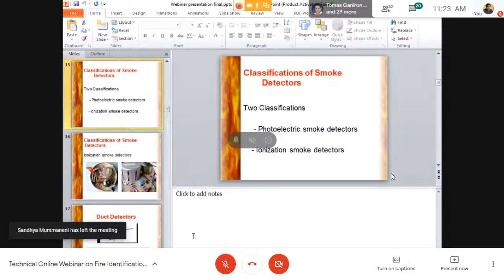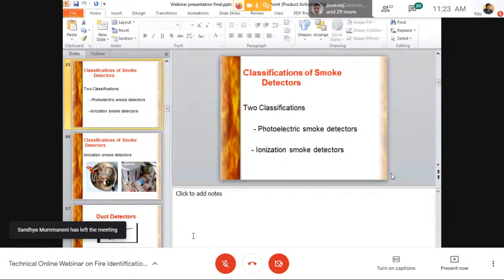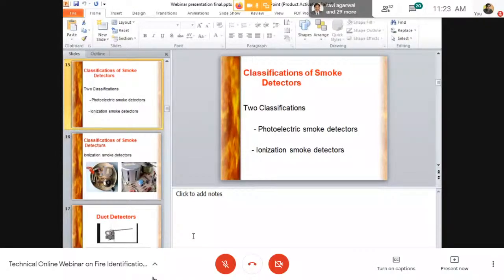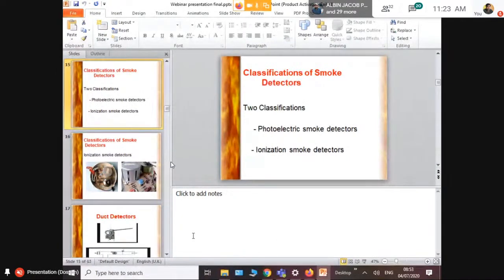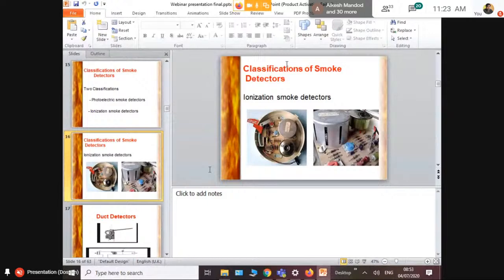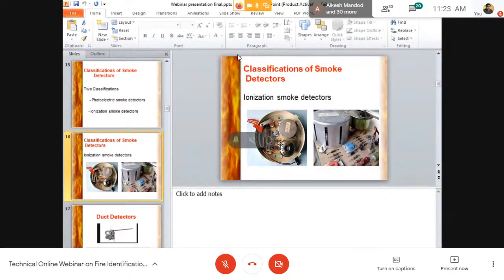Photoelectric is something like, the smoke hits the photoelectric sensor inside the smoke detector, and the alarm is given to the fire control panel. Ionization detectors are the same. You have two conductors inside where the conduction is disturbed by the smoke, and you get a smoke detection. This is an arrangement of what you see inside an ionization detector. This is how it is. Too complicated compared to what you see in photoelectric detectors.